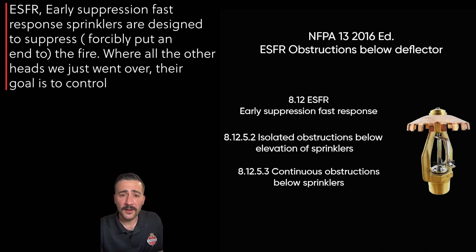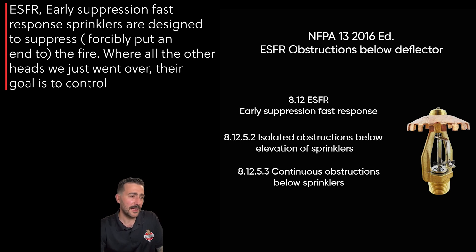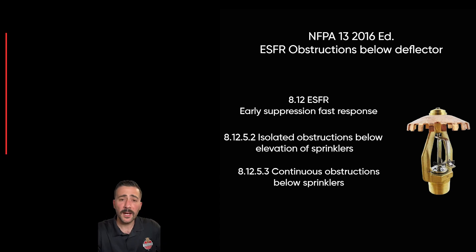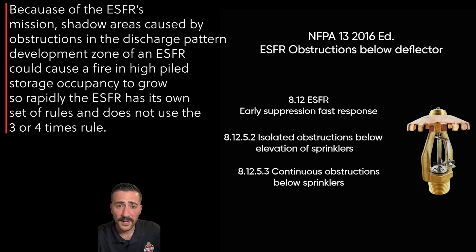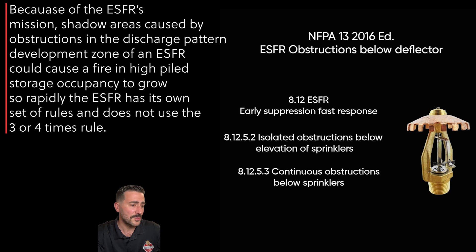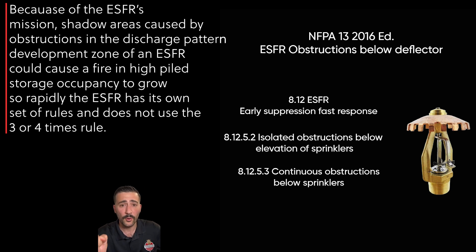The ESFR early suppression fast response sprinklers are designed to suppress the fire, whereas all the other style heads we just covered are designed to control it. Because of the ESFR's mission to suppress the fire, shadow areas caused by obstructions in the discharge pattern development zone could cause a fire in a high-piled storage occupancy to grow so rapidly that the ESFR has its own set of rules and does not use the three or the four times rule.